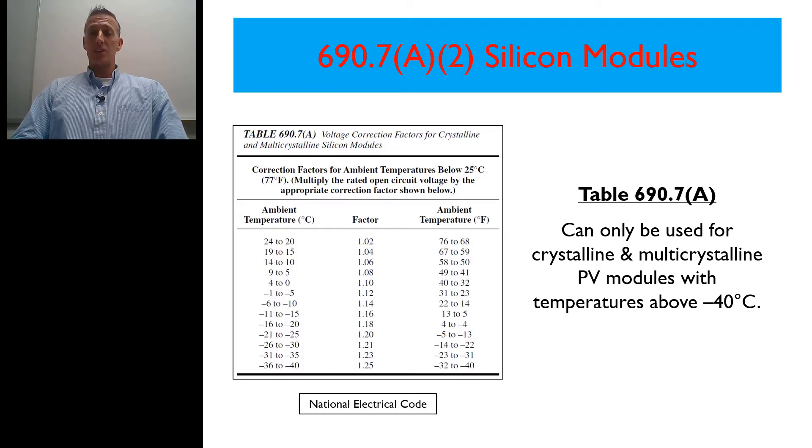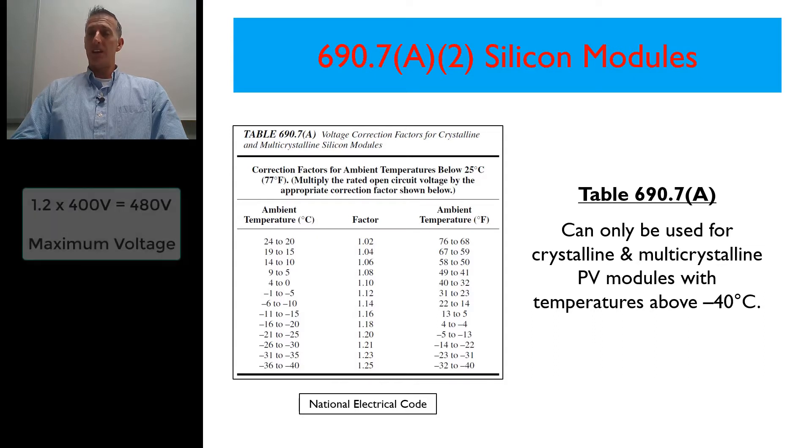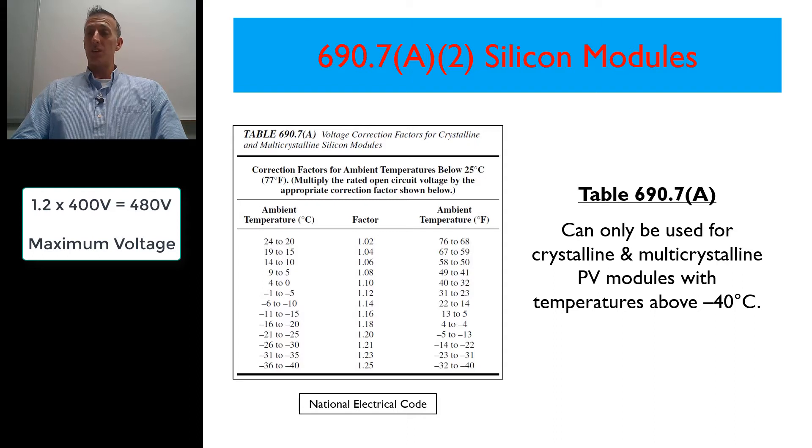At that lowest expected temperature using this table, we would take 1.2 times 400. And that would give us the total high or the maximum voltage that we'd expect to see out of that system. So that's how we would use this table.